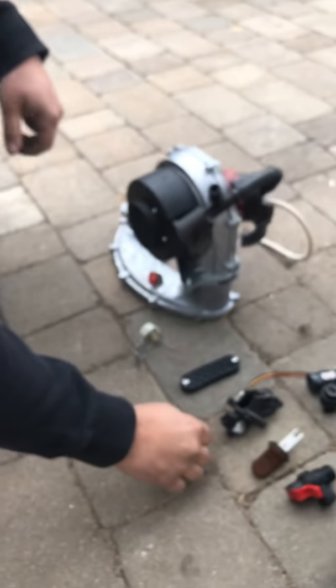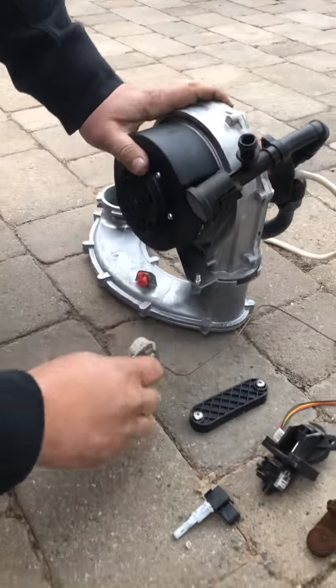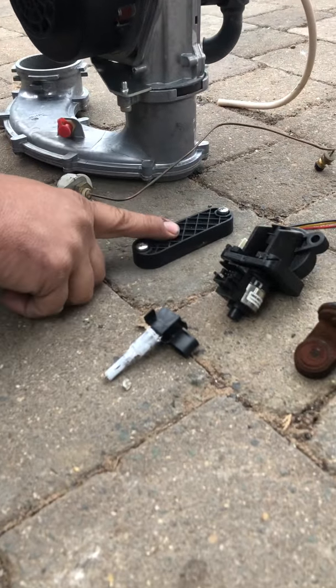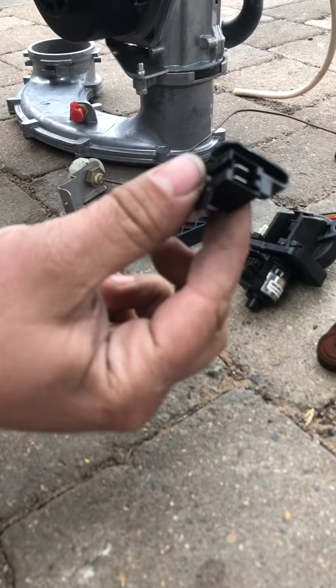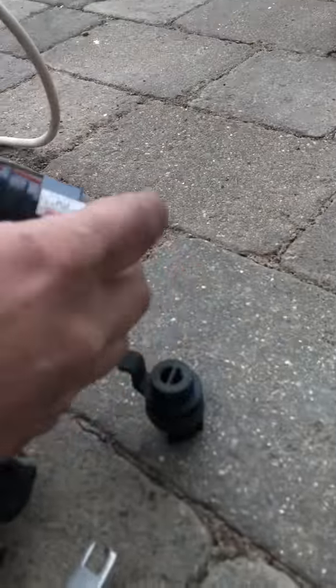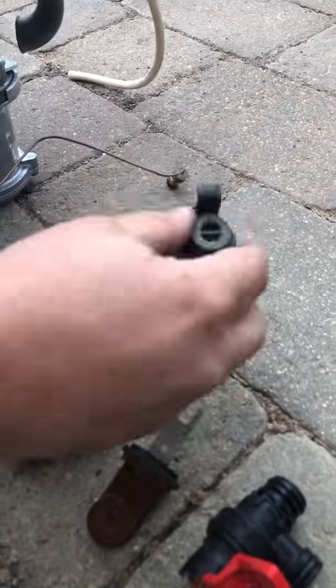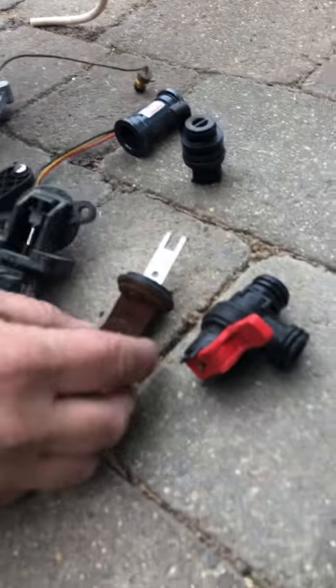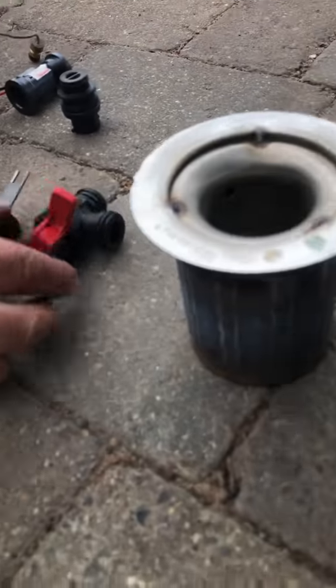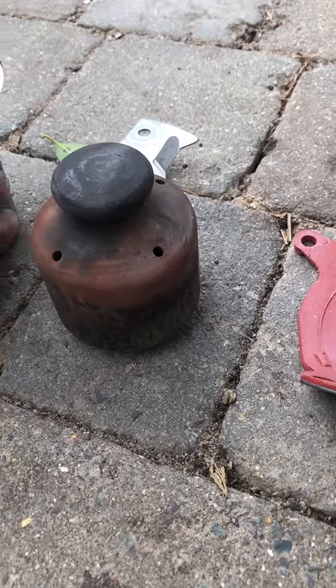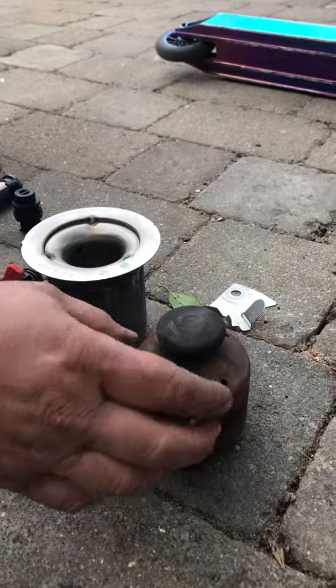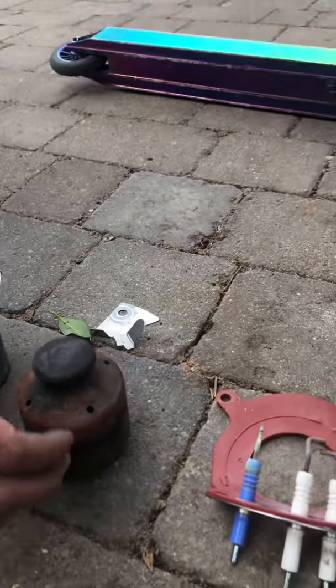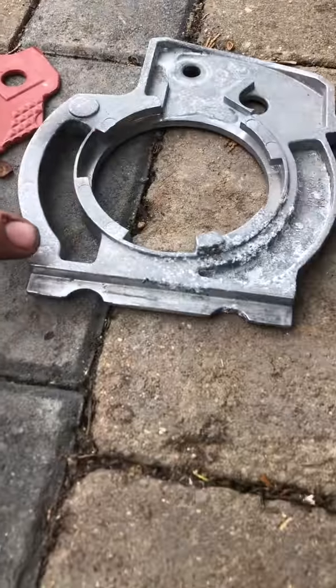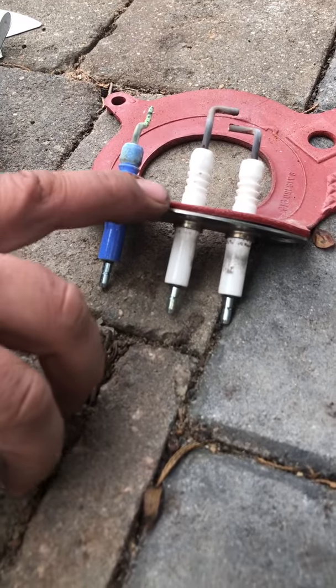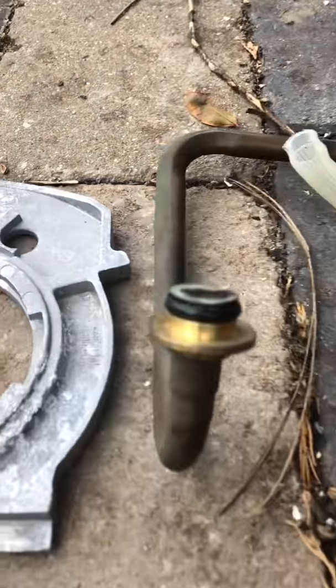And we'll just go through what we've actually done here. So we've nearly stripped this boiler down completely. We've got the fan assembly taken out, the pressure gauge taken out, the sump inspection cover, the boiler thermostat, the flow turbine sensor and the flow turbine adapter, the diverter motor, the diverter paddle, the pressure relief valve, the burner, the baffles, which go in first, and then you slot that in after into the main heat exchanger. The locking plate there, which holds this unit together, sits on top of that one. The electrodes and the burner seal, and the cold pipe there we just took off with the filtering.